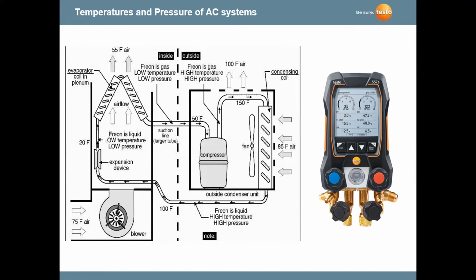And as you know, most of your customers, unless you're dealing in the commercial market, most of the homeowners, residential customers, can't grasp this cycle as much as you can because they're not studying it every day as you are. But again, pressure and temperature measurements are very important. As I said in the beginning, it's very critical now because we have less forgiving refrigerants. We're going to have a lot of new refrigerants coming in 2022, I believe, higher SEER, higher capacity ratings on our equipment, leading to a change from the traditional tools that we've been using. And when we change from traditional tools to digital tools, it's really all about the accuracy of the measurements that we're taking.